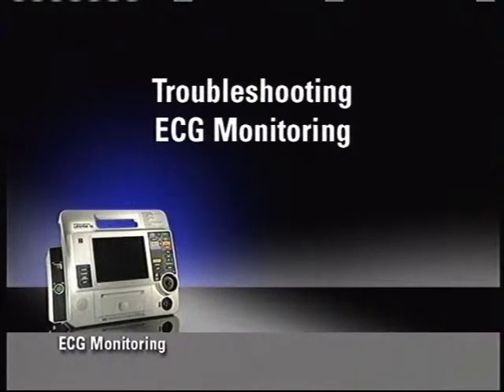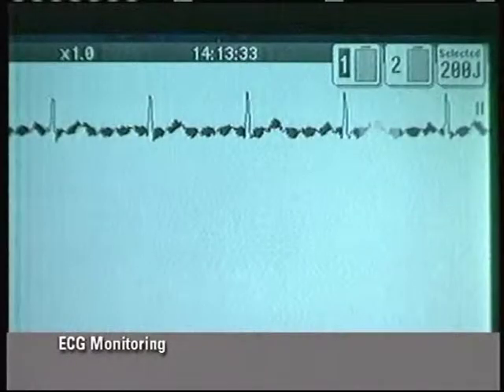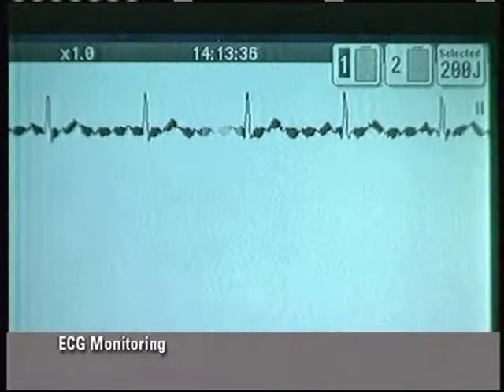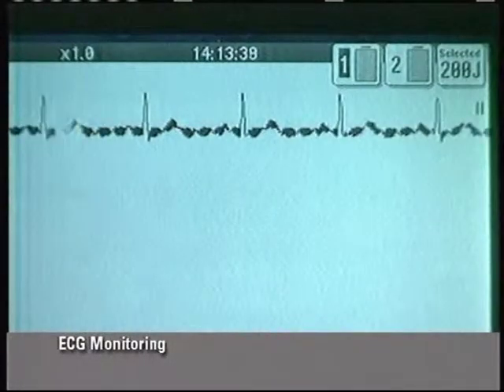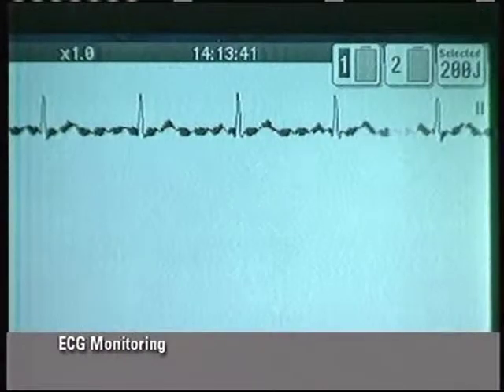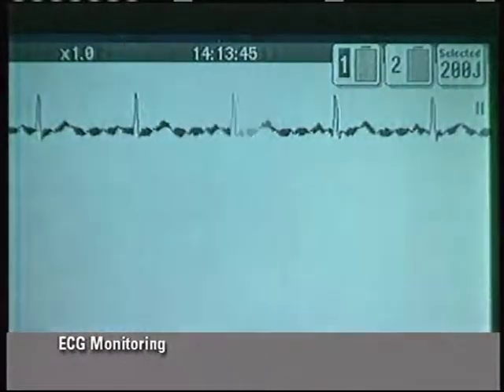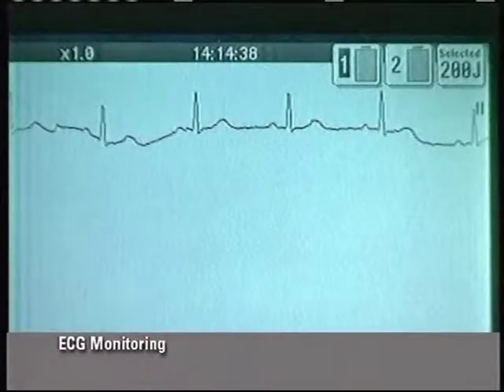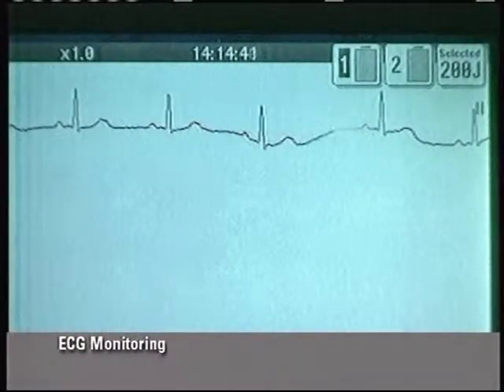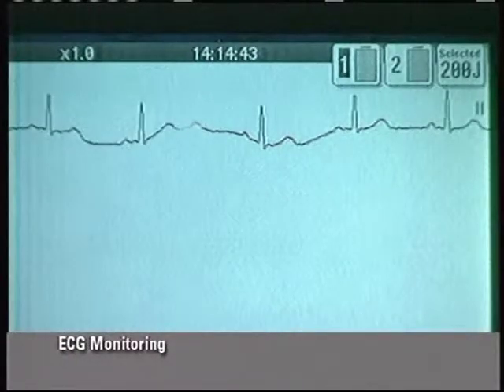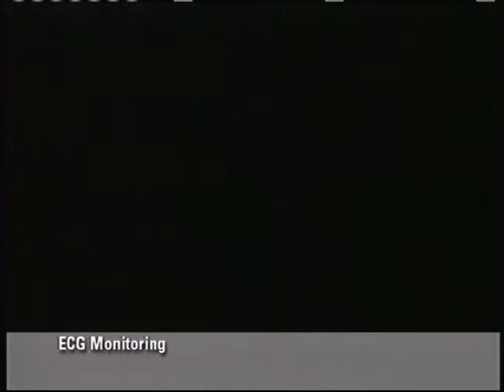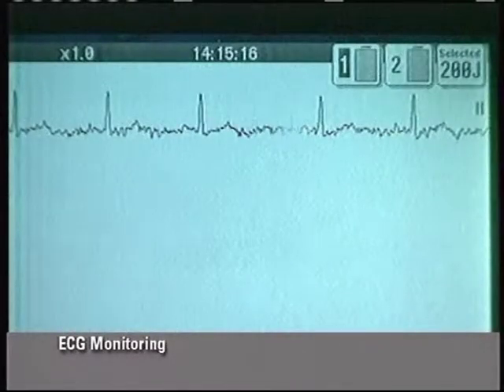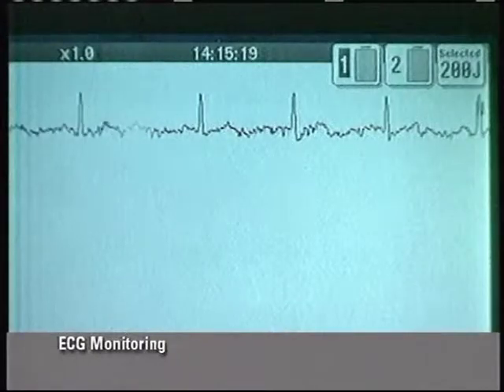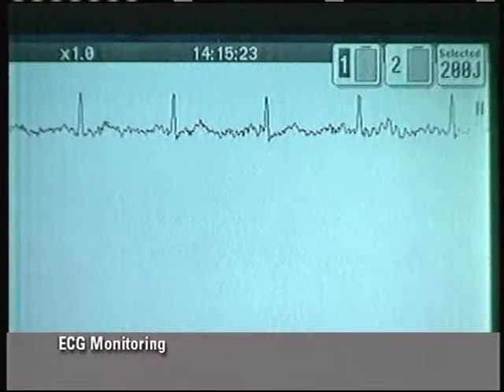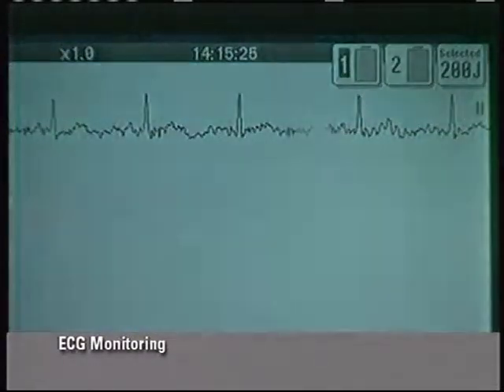The most common problem encountered with ECG monitoring is poor ECG signal quality. High frequency or 60-cycle interference may be caused by equipment connected to the patient that is improperly grounded. This may be temporarily corrected by operating the other equipment on battery power or unplugging unnecessary equipment. Baseline wander may be due to the patient's breathing. This may be corrected by repositioning the ECG electrodes to an area with less movement. Two other reasons for poor ECG quality are using outdated electrodes and inadequate skin prep. Always use fresh electrodes and prep the skin as previously described.